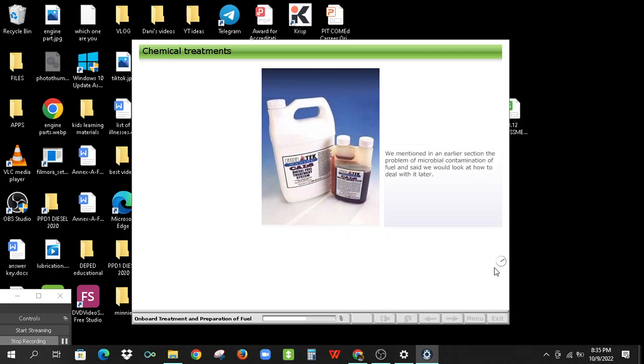We mentioned in an earlier section the problem of microbial contamination of fuel, and said we would look at how to deal with it later. The condition requires the use of chemical treatment in the form of a biocide. Biocides and other chemical additives are widely available to deal with this and other fuel-related problems. Some of these treatments can be added at the storage stage, but most are designed for use in and after the service tank. We are not going to look at the chemistry of the additives here.